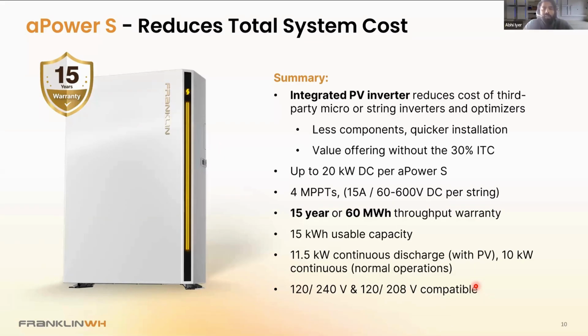You can land up to 20 kW of PV DC to a single aPower S. That means you can land up to 4 MPPTs, at 15 amps per string. As far as the overall acceptable voltage ranges go for the entire system, that's 60 to 600 volt DC—pretty standard with regards to what you see in the industry today.